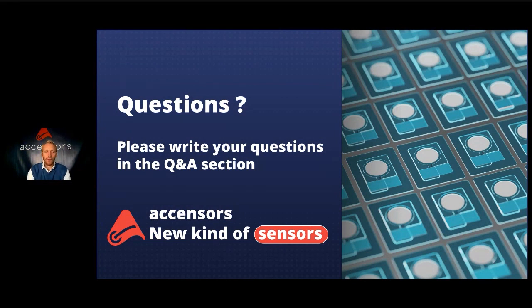But we will also create different sensor solutions for the same parameters. This means sometimes you need a quick sensor. So you put a blood drop on the sensor and you want to get a result immediately. So you need a really, really short setup time. But the shelf life or the measurement time is not so important. And sometimes you have a long process, a biofermentation process or something, and the setup time could be 6 or 8 hours. It doesn't matter, but you want to measure over 4 weeks. This could be the same parameter you want to measure, but the time of use is totally different depending on the application.